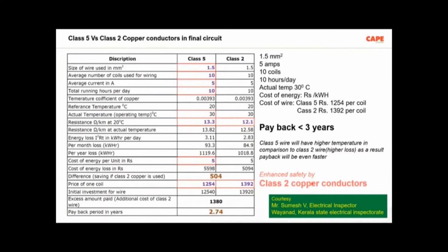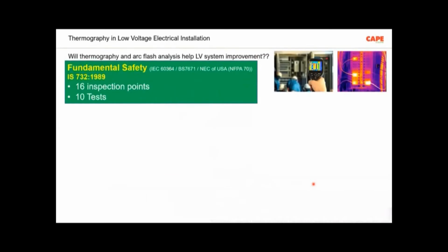And what additionally you get is increased safety with a class 2 conductor, because at the end of the day, in case of an overcurrent, a short circuit, or an earth fault, the protective device should trip. For the protective device, especially an MCB, to trip, the fault current comes into the picture. Once the fault current comes into the picture, the impedance of the circuit comes into the picture, and the impedance is greatly affected by the resistance of the conductor. So this is a very, very important subject.